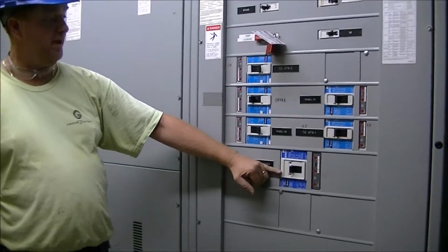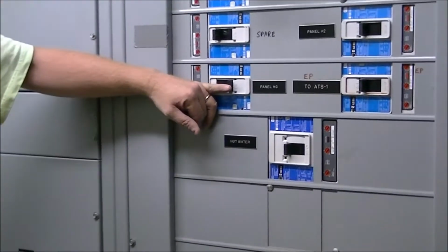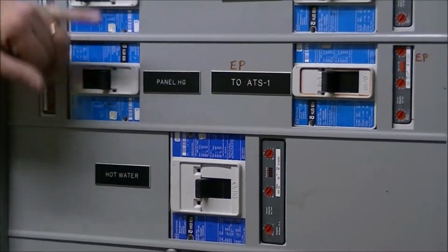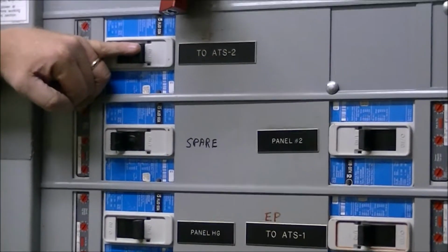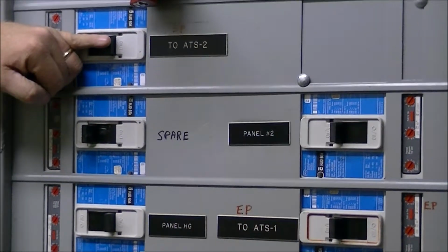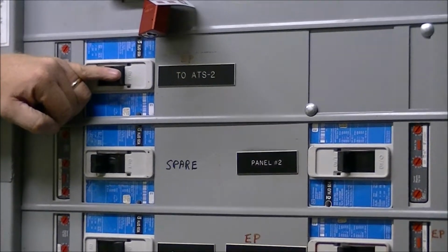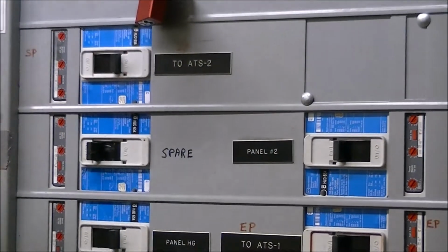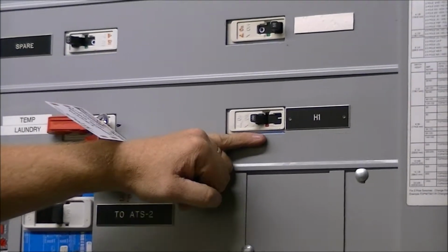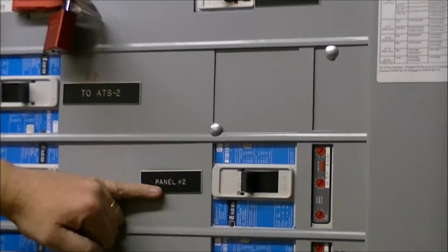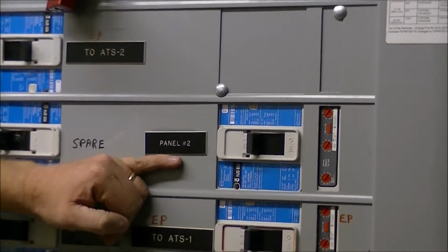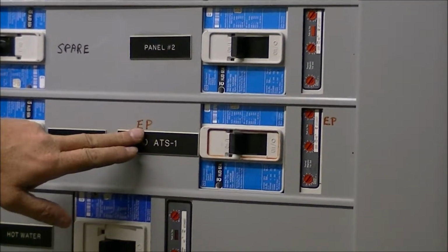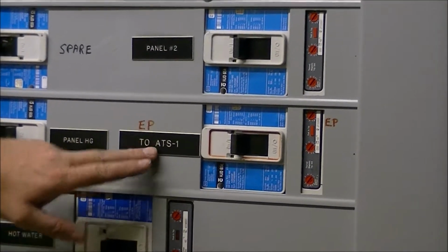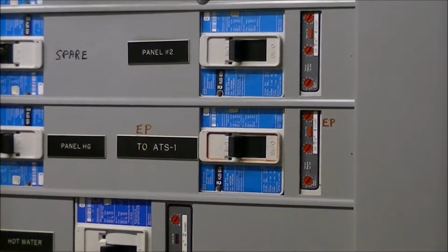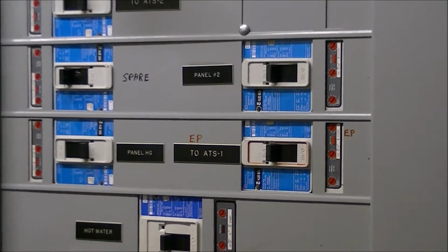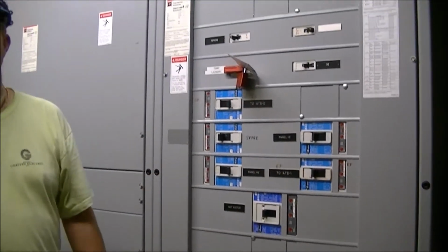Got a hot water panel that's in the penthouse. Panel HG is where we've just come from. We see them labelled up. ATS2. So this is the 480 supply that feeds the ATS, the automatic transfer switch, and then obviously over to the generator, and then back from the generator to ATS2. So standby power. Got panel H1, which is located on the first floor, which we'll see as we go up. Panel H2, this is located on the second floor, and we'll see that as we go up as well. Again, all 480 277. ATS1 EP, emergency power. Again, 480 277 to the transfer switch, out to the generator, and then back again when any power goes out. That's all you need to worry about down in this section.